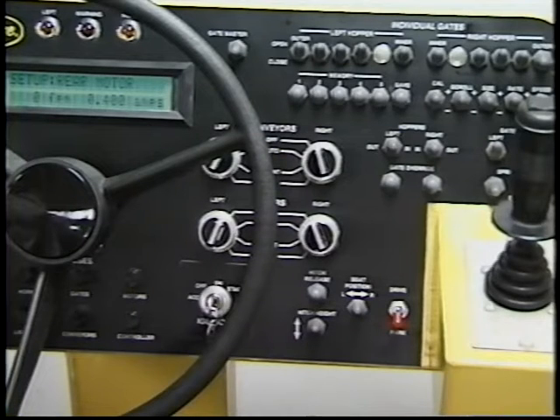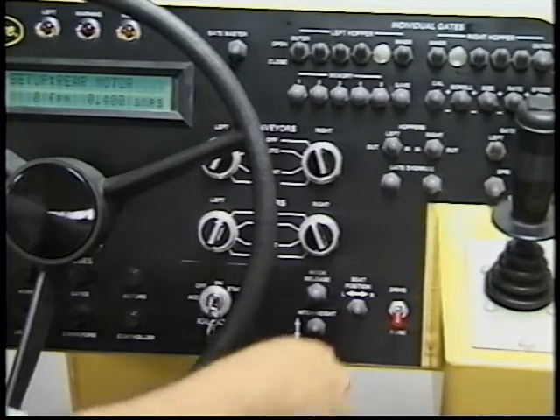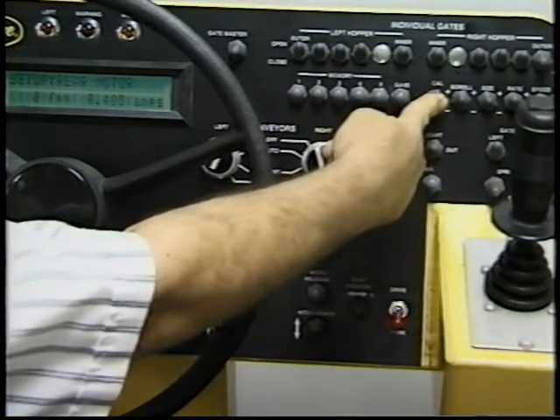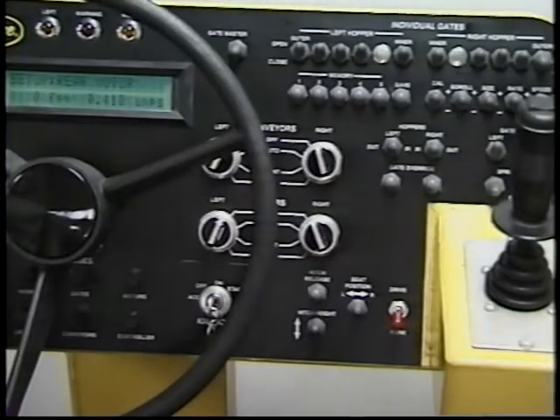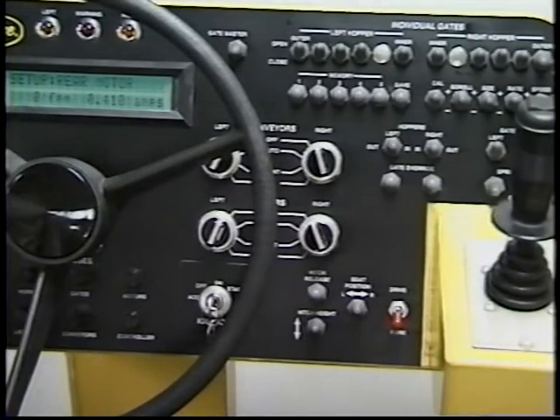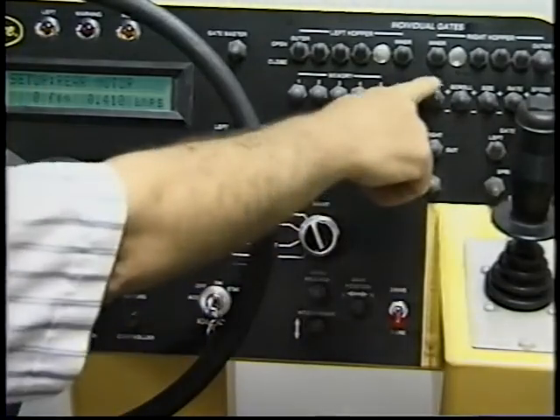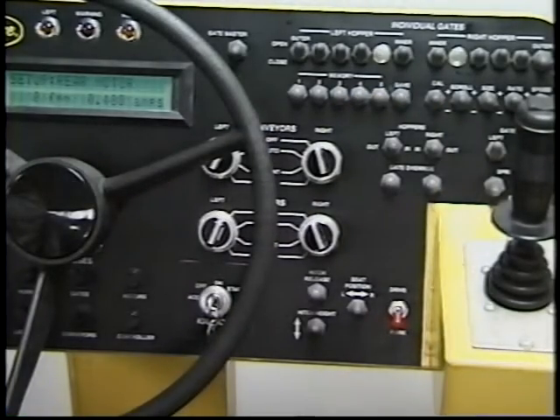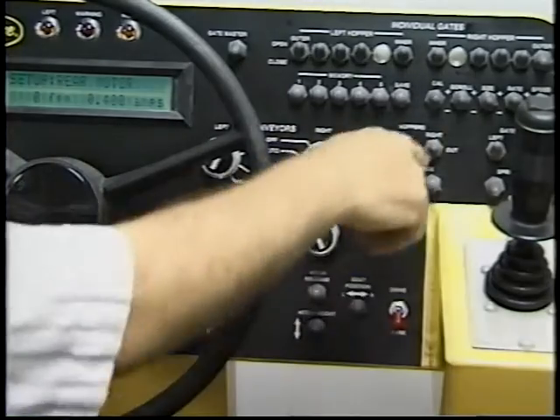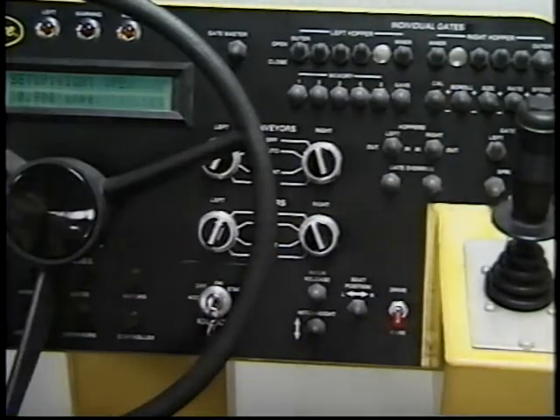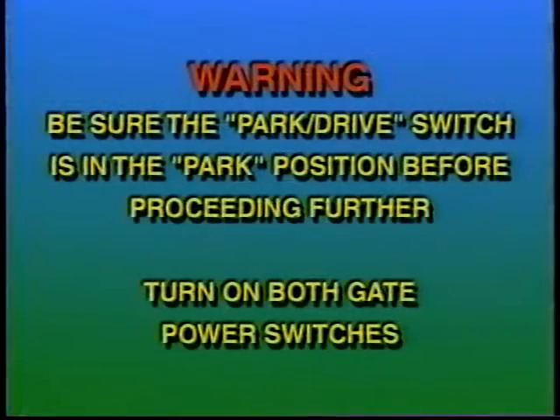Operate the chip spreader at 300 feet per minute. While the chip spreader is running at 300 feet per minute, increase the threshold current until a change in speed is felt, and then back it down until there is no speed change. The normal threshold current setting from the factory is 0.400 amps. When it is set to this value, push the scroll switch down to move to the next screen.